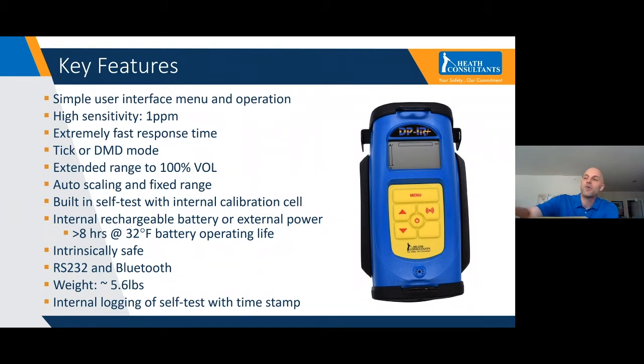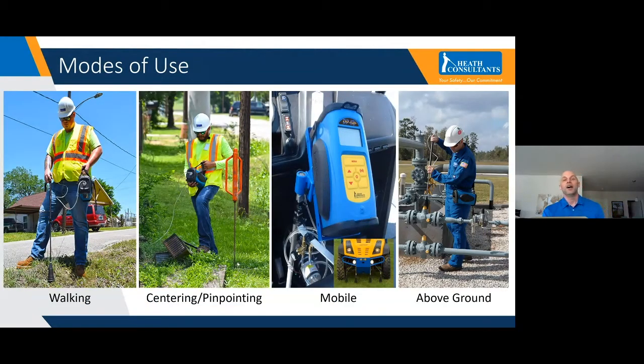Fairly lightweight instrument, weighs about 5.5 pounds. And then I mentioned the self-test that we recommend doing once a day. Those records, when it's done, it's all kept internally on the instrument. So if you ever need to download that information, it's all stored on there. So it's easily accessible to get that information off there too. Some of the main methods for using the DPIR, firstly is for walking survey.